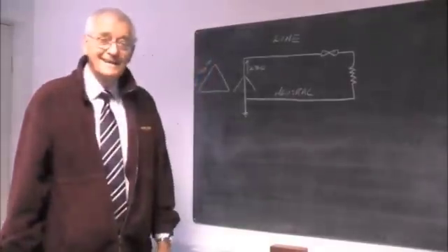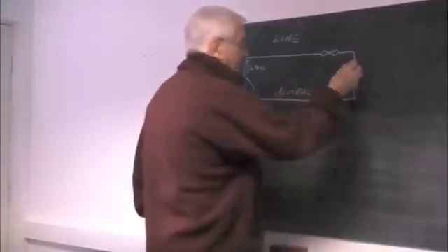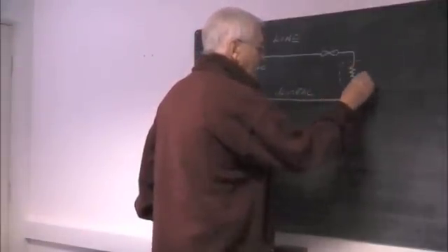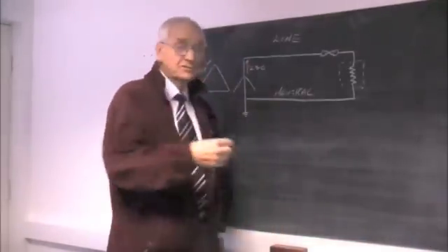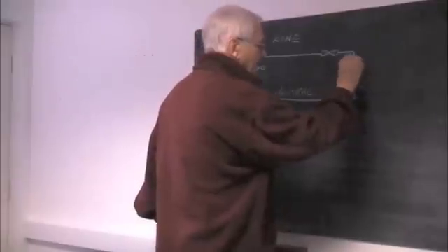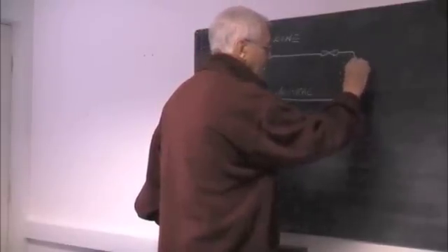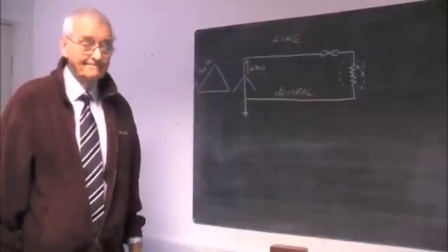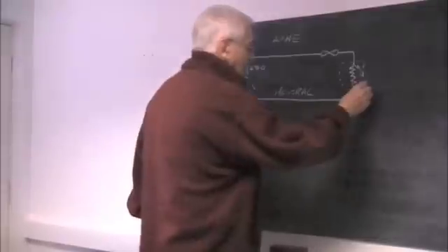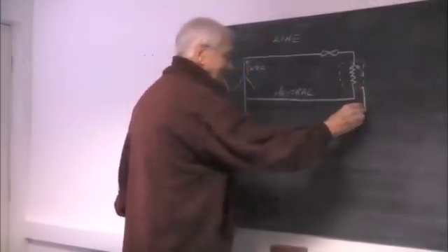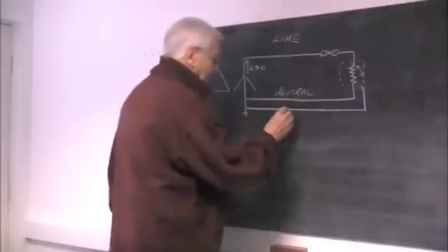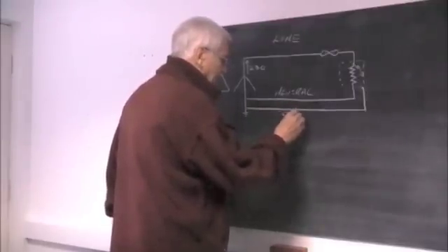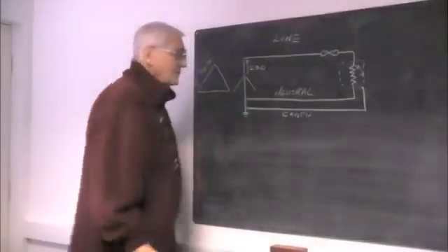Okay, that's fine. Now this will be contained normally in some sort of exposed conductive part which is metallic, for example a distribution board. If you have a fault on it, then you may get a fault from the line conductor to the exposed conductive part of the piece of equipment that you're testing. This piece of equipment will be connected to earth and we'll show it as a TNS connection for the moment. That's where the neutral and the earth conductor or the earth bonding conductor are separate.